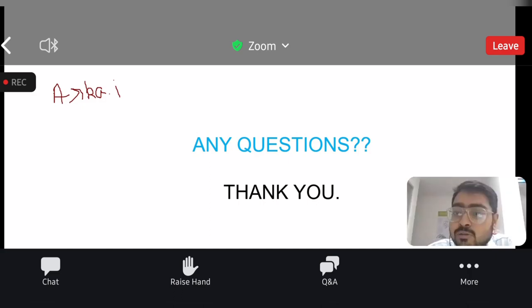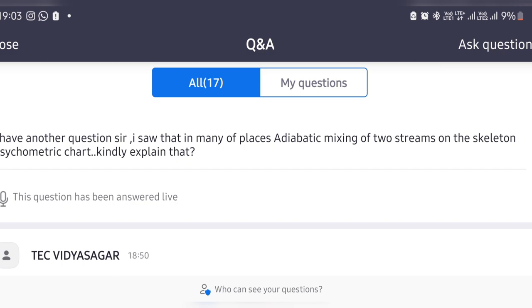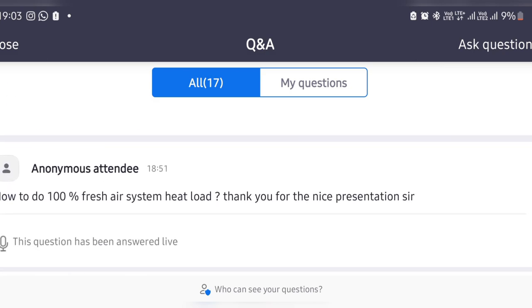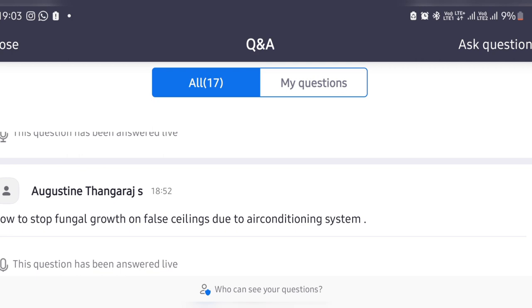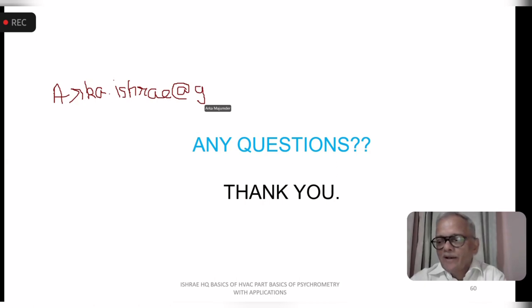Mr. Augustine has asked how to stop fungal growth on false ceiling due to air conditioning system. Sir, if you could address that. How to stop fungal growth in false ceiling. See, fungal growth will be observed on surfaces which become damp. Now, the surface will become damp when you have a condensation of moisture. And condensation of moisture happens once you have stagnant air, a surface which is at a temperature lower than the dew point of the air, and moisture. So when you have all these three together, you have a damp surface. And if that damp surface is an organic material, like a canvas cloth typically, or any material which has an organic origin, in such condition, it is definitely going to have fungus.